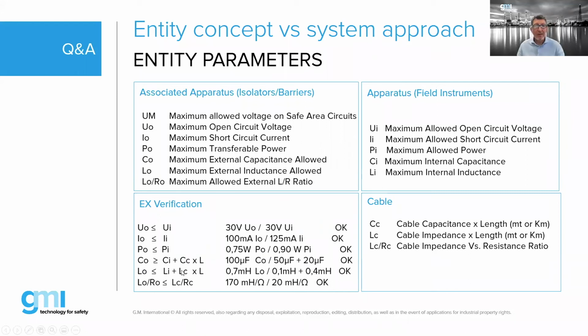It's Ex certification verification. You have the maximum allowed voltage that the barrier will provide into the field. In this case, we have picked 30 volt as an example, which must be equal to or lower than what is allowed by the transmitter in the field. So if the transmitter is certified for a maximum of 30 volt, the barrier should guarantee that no more than 30 volt are sent to the transmitter.